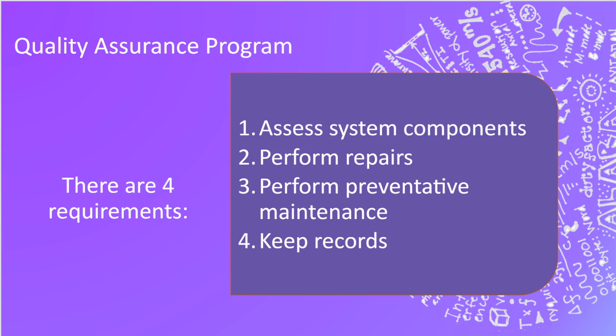You want to make sure that you use that check-off list. It'll be your records that you'll want to keep. Make sure that you get everything, keeping that routine and periodic portion of the quality assurance going. If you were to find anything abnormal within that check, then you're going to do repairs. So if a fan is broken, repair it. If a transducer is broken, send it out to be repaired, and so on.